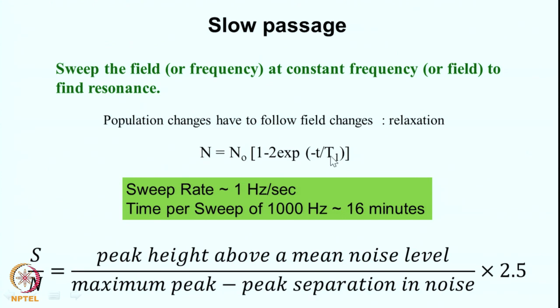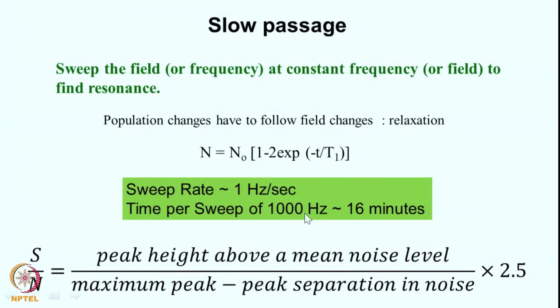If T1 is of the order of seconds, you cannot sweep the field too fast, otherwise you will not be reaching an equilibrium situation at every point. Typically, sweeping at 1 Hz per second over a spectrum of width 1000 Hz — which corresponds to 10 ppm on a 100 MHz spectrometer — would take approximately 16 minutes for one sweep.